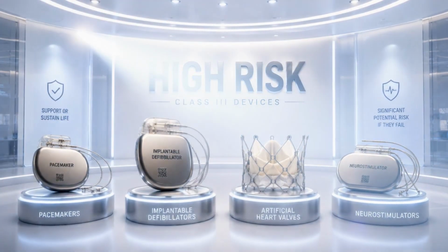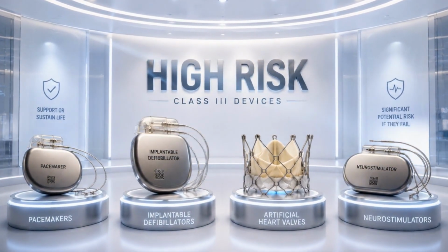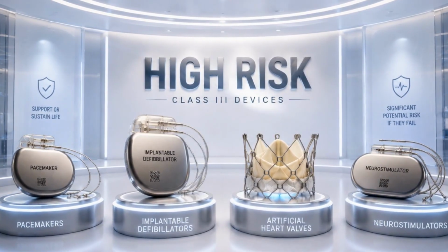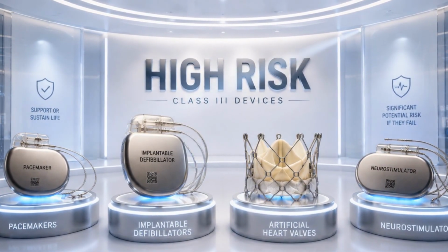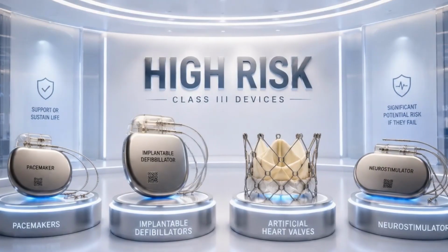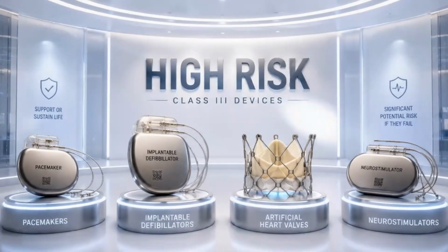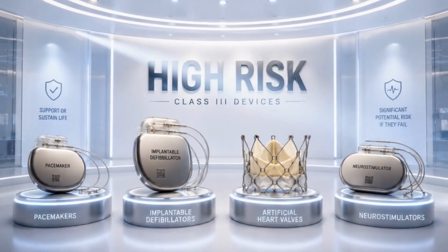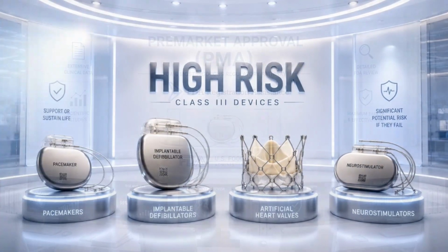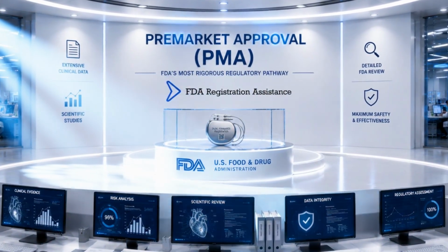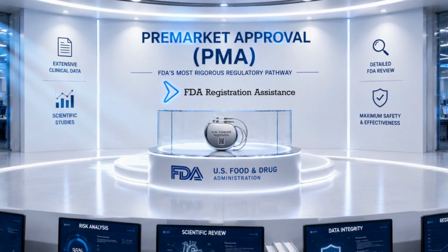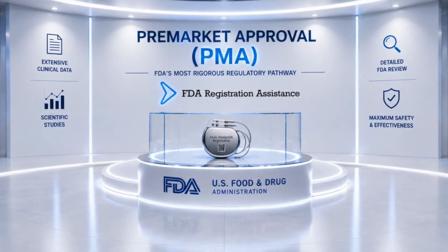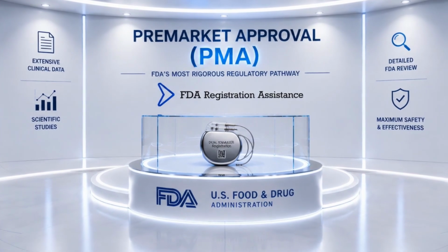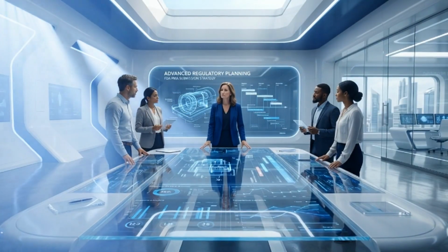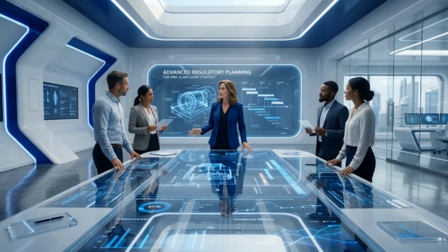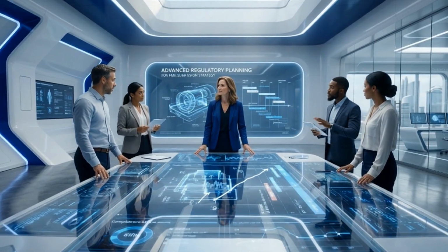Class 3 devices are considered high-risk medical devices. These products often support or sustain life, are implanted into the body, or present significant potential risks if they fail. Examples include pacemakers, implantable defibrillators, artificial heart valves, and certain neurological implants. Class 3 devices usually require pre-market approval, also known as PMA. This is FDA's most rigorous regulatory pathway and often involves extensive clinical data, scientific studies, and detailed FDA review. Because of the complexity involved, Class 3 compliance projects can require substantial regulatory planning and documentation.